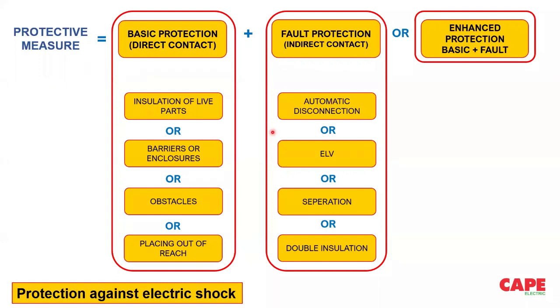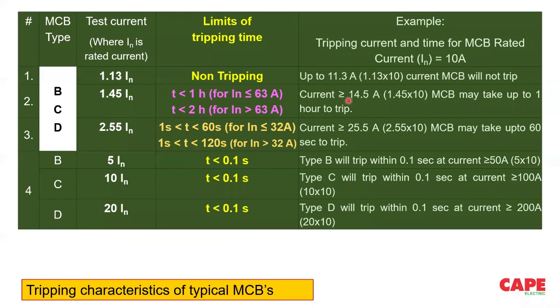So this is the meaning of, out of 18 inspection points, the first inspection point: protection from electric shock. The verifier must understand each of these measures, and he has to find out the applicable measure which is applied in a specific location. Now, when it comes to automatic disconnection, which is one of the safety measures, especially used in AC application, MCBs are used for automatic disconnection.